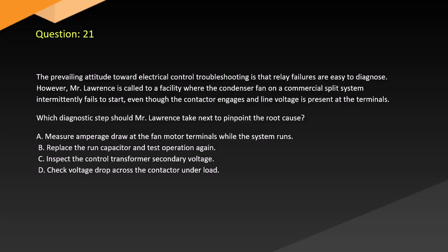A. Measure amperage draw at the fan motor terminals while the system runs. B. Replace the run capacitor and test operation again. C. Inspect the control transformer secondary voltage. D. Check voltage drop across the contactor under load.